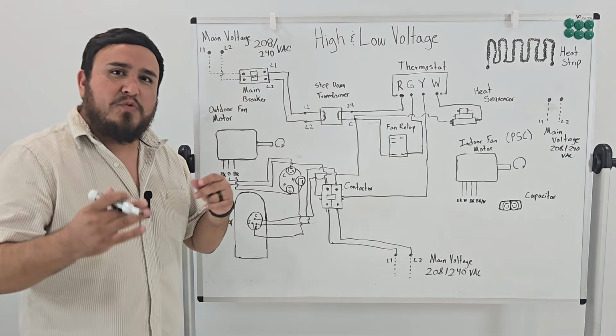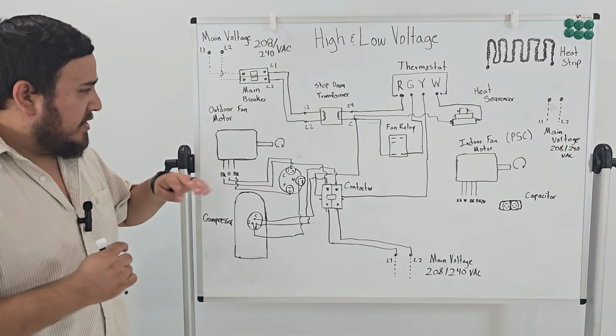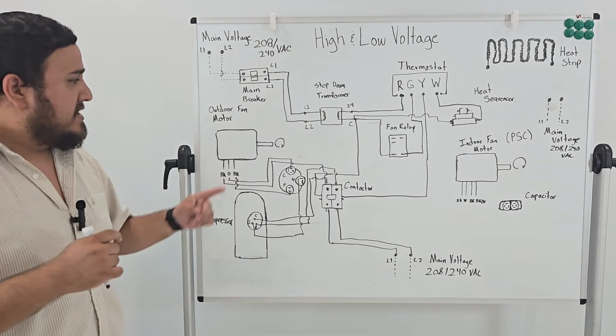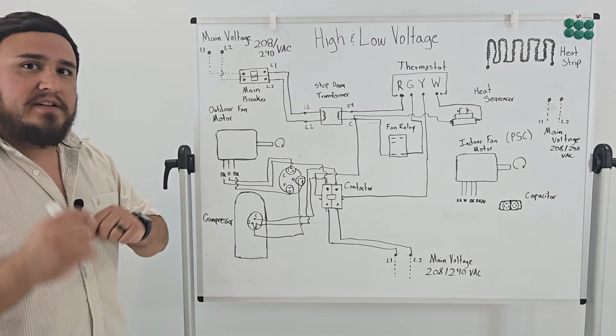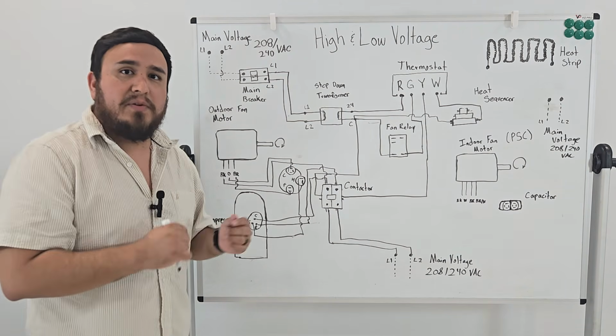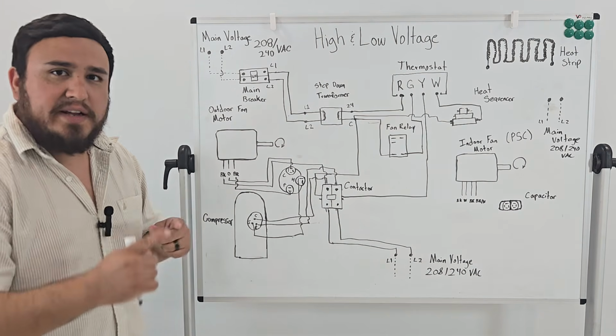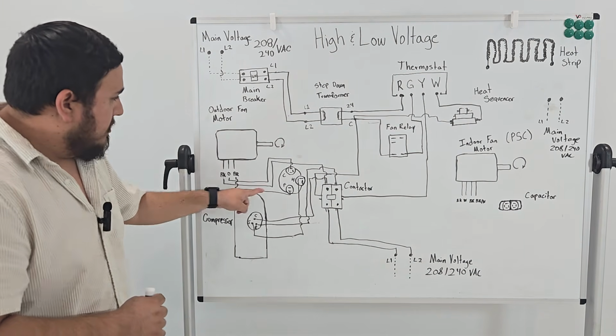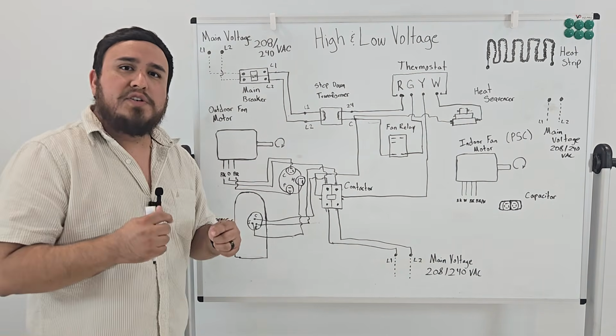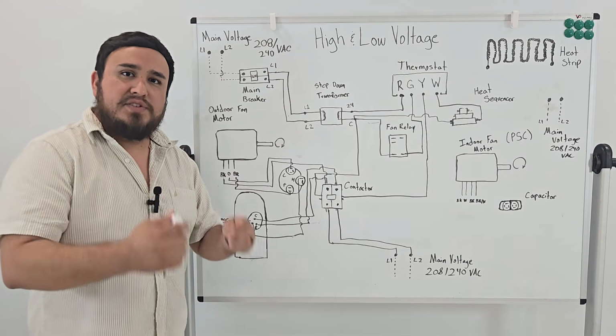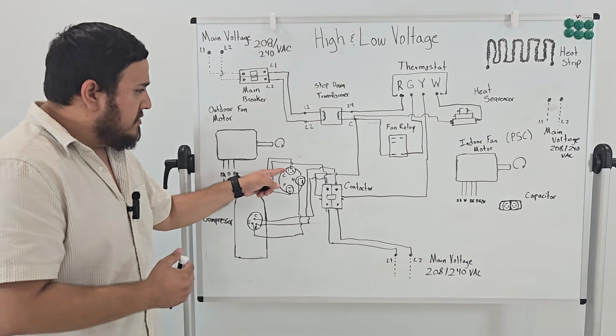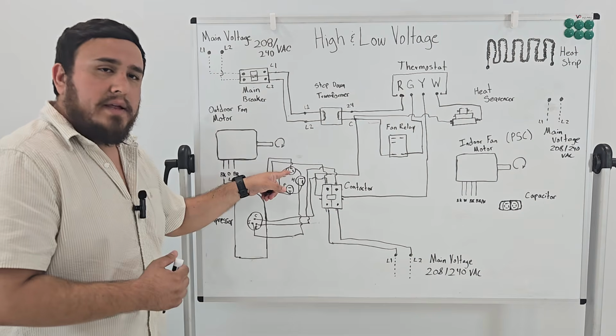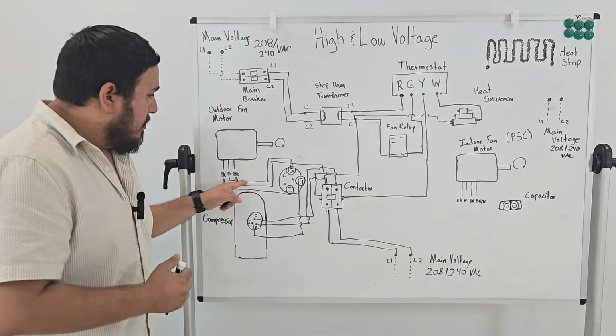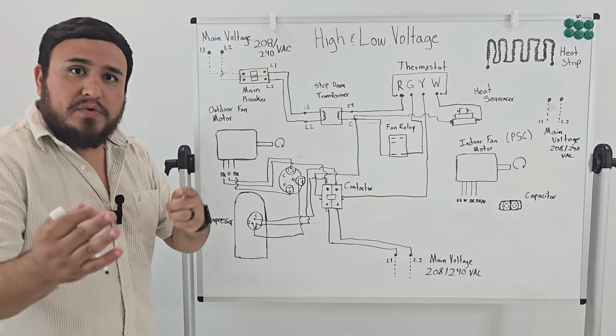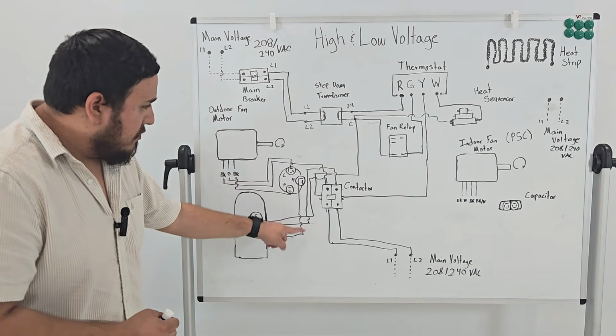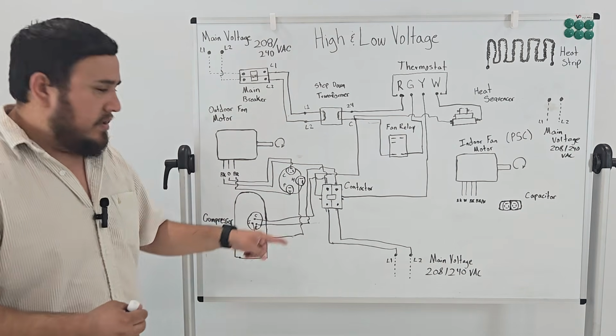All right, so the wire that we actually need to connect is another common wire, or line 2, to my common for my fan. Why do I say this? Because check it out. I have black going into the L1. My orange wire is actually line 2, but as you can tell, line 2 is just going directly to my capacitor. So that means my orange is going to my capacitor, but so is my start wire. My start wire is going to my capacitor.